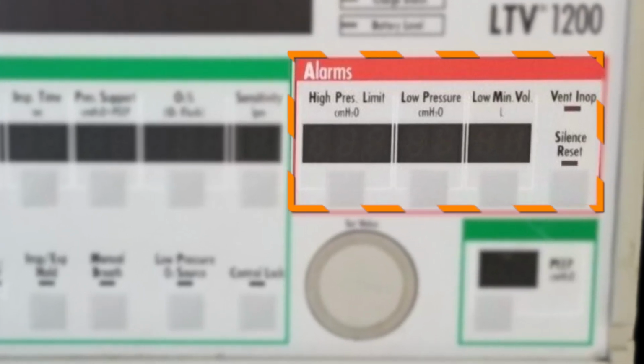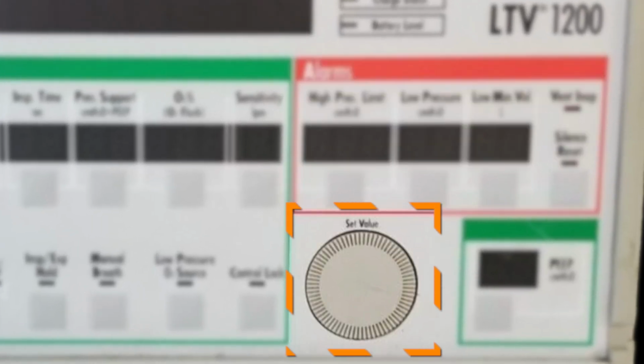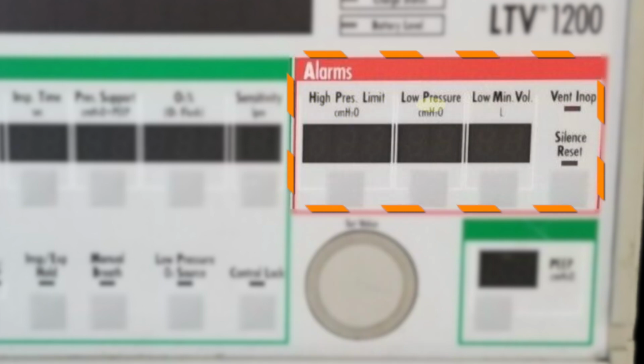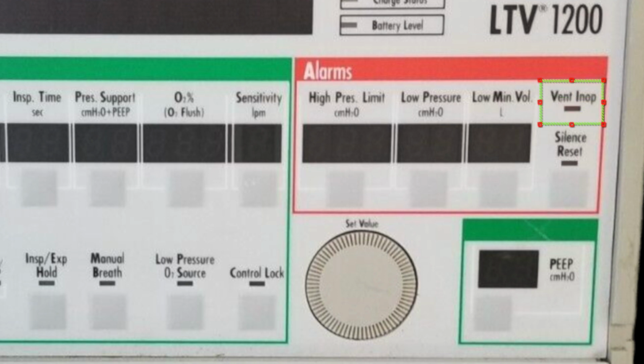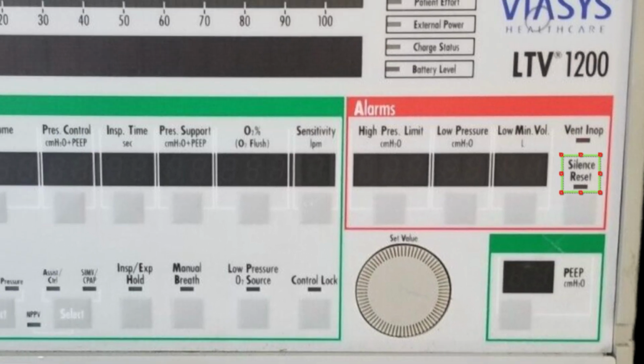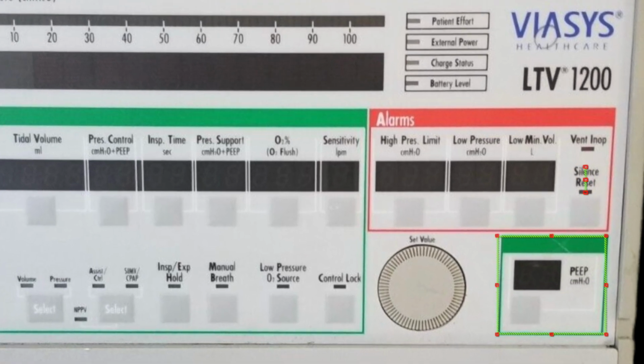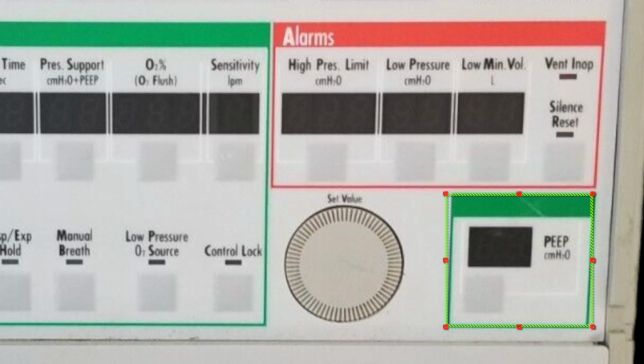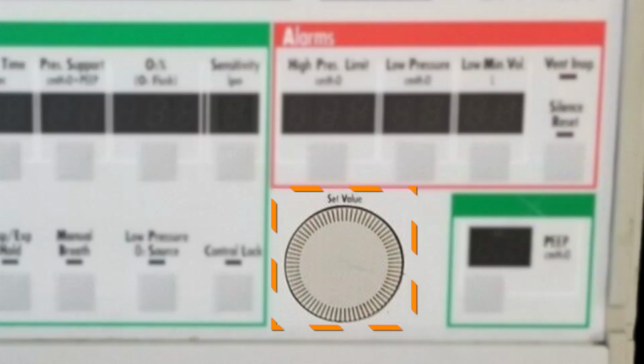You can use the set value knob and change parameters for high pressure limit, low pressure, and low minute volume. This LED indicator for vent inop becomes lit for a minimum of 5 minutes once the ventilator is turned off. The silence reset button can be used to silence alarms when appropriate. And at the bottom right is the PEEP control setting and display. Notice the set value knob.